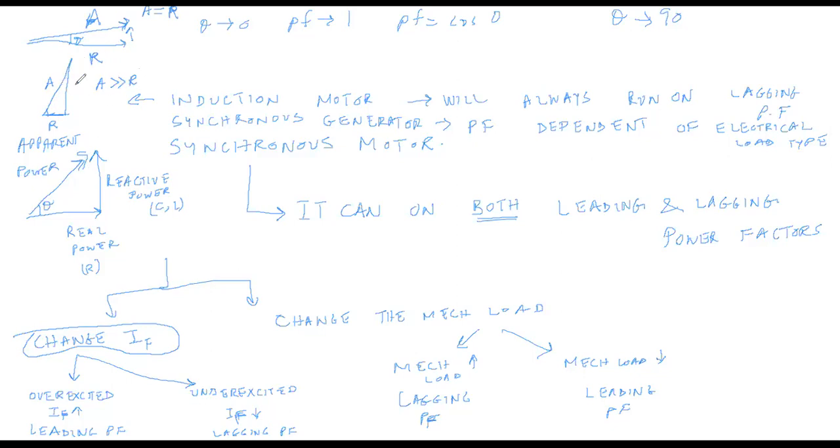So bringing back to the discussion, why would you want a synchronous motor to run in a leading power factor? It is so that you could use it as a power factor correction device. And what is a power factor correction device? For example, you have a large amount of inductive loads in your home, like induction motors and ceiling fans. So your power triangle will tend to look like this, and in order to make it look like this, you are going to attach capacitors.